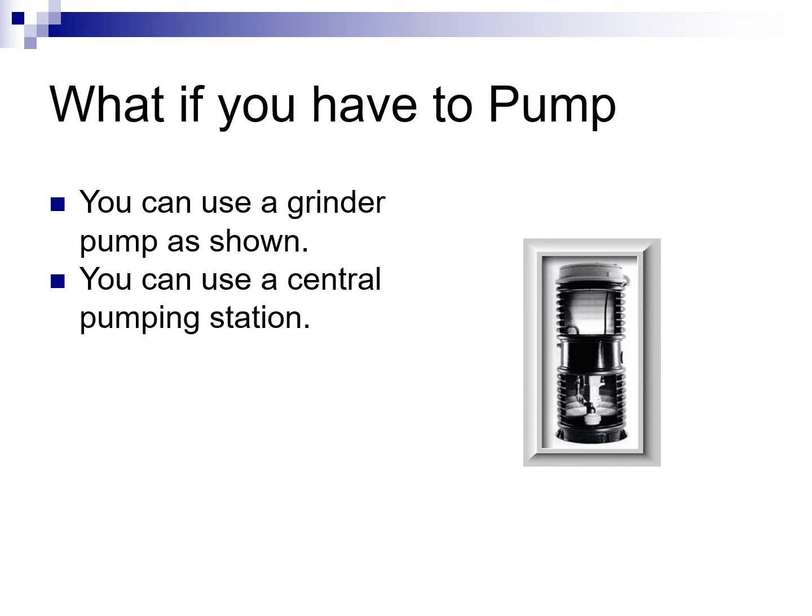Also, if the whole neighborhood is actually lower than the pipe they're trying to tap into, you might have a central pumping station where, let's say, 10 houses on a cul-de-sac will all go into, by gravity, a central pumping station, and then there will be a pump there that then pumps all of their sewage into the municipal sewage system.